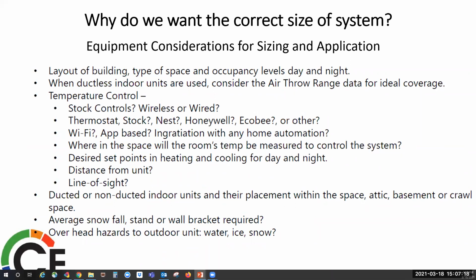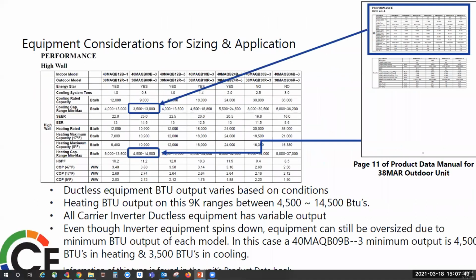Why do we want the correct size of system? Choosing the correct size and the right type of equipment is a critical part of installation. You always want to refer to your product data to see that the equipment operates together, and to see its temperatures and BTU ratings. One thing to remember when you are installing ductless systems: they are variable speed. They do not operate like conventional heating and cooling equipment. Correct size and type of installation is very important, depending on where the application is. Remember, these are variable speeds, so the heating and cooling outputs are not set in stone.